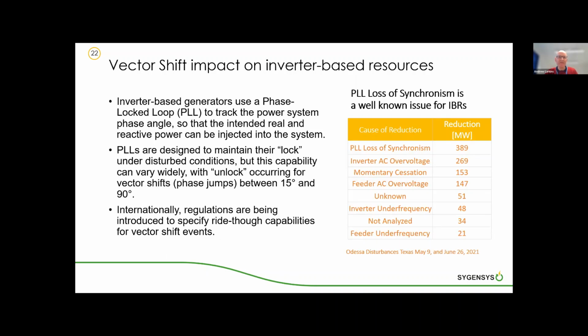So the next area we looked at was vector shift impact on inverter-based resources. Inverter-based generators use a phase-locked loop to track the power system phase angle, so that the intended real and reactive power can be injected into the system. So from the inverter side, they have to know what the power system phase is, so they can set their own phase to inject the right amount of real and reactive power.